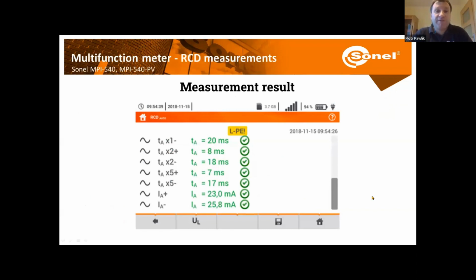Okay, and with our multifunction meters of the MPI series, we have a special function called RCD auto measurement, and it allows us to check all the parameters of the RCDs, and also RCDs of different types: AC, A, F, B, and B+. So here we can check the triggering current and triggering time of the RCDs for nominal current times 1, 2, or 5, or half. In case the RCD triggers when we test with half the nominal current, that means that it is too sensitive and therefore faulty.